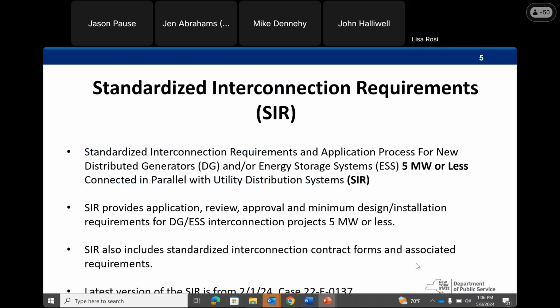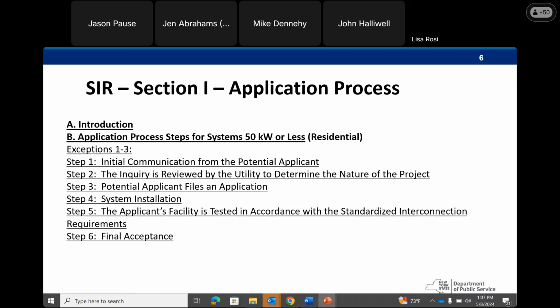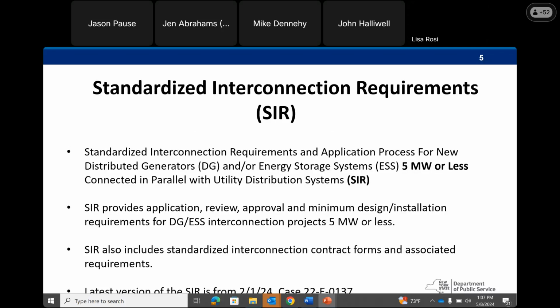One of my roles and responsibilities is administering and looking after the Standardized Interconnection Requirements of the Commission. The SIR applies to new DG and energy storage systems 5 megawatts or less connected in parallel with the utility distribution system. It provides application, review, approval, and minimum design installation requirements for DG and ESS interconnection projects, and also includes standard contract forms and associated requirements. The latest version of the SIR is from this past February 1st, 2024, modified in case 22-E-0137.